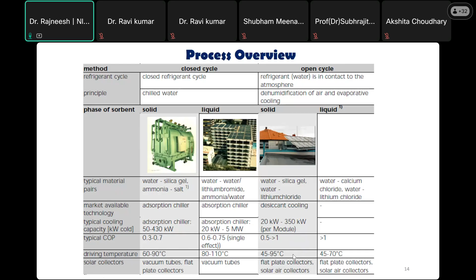In the open cycle, we have all the things available. In open cycle, the COP is a little less, 0.5 to less than or equal to 1. Temperature range is 45 to 95 degrees, and 45 to 70 degrees in case of liquid, since the regeneration temperature required is a little less as compared to the solid ones and the closed system cycles.